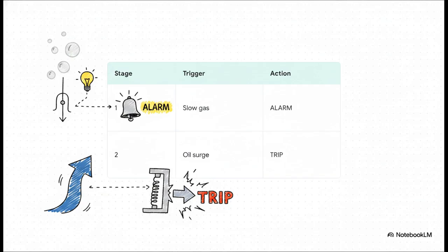It's basically the transformer saying, hey, something is quietly degrading in here. But let's say there's a massive, sudden internal short circuit. That creates a violent shockwave, causing a rapid surge of oil up the pipe. That physical surge slams into a second mechanism in the relay, triggering stage 2, an instant, direct trip to shut the whole thing down immediately.